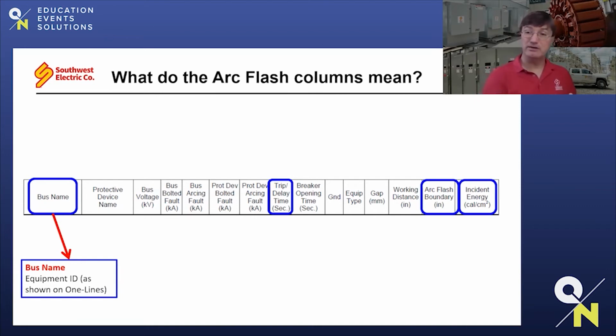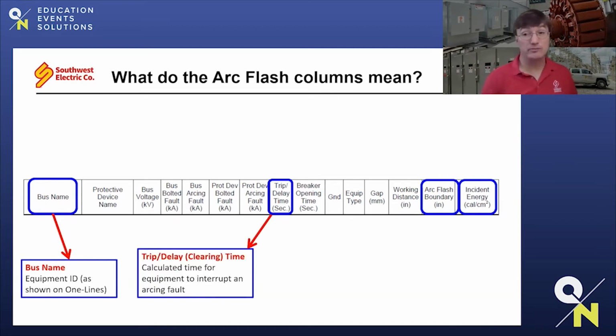This is usually the piece of equipment in your facility that we are analyzing. If that piece of equipment were to have an arc event, what would happen? So we identify that piece of equipment. Every piece of electrical equipment will end up being identified in this assessment and should receive its own label. The trip delay time, sometimes called the clearing time in seconds. This is the amount of time the system requires to clear a given arc fault. That time is based on the coordination settings of either fuses or protective relays that are throughout the system that apply to wherever that arc fault could occur. The lower the time this is, usually the lower the incident energy will end up being.